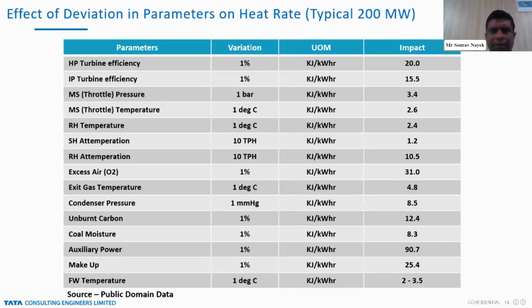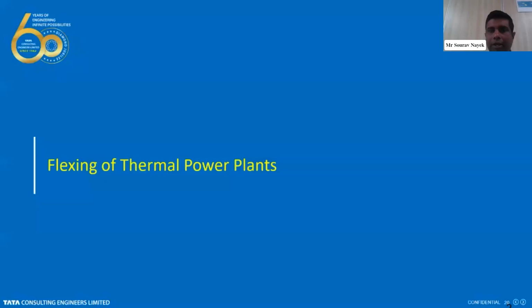We have captured the different parameters and how they impact the heat rate, like the turbine, condenser, and different boiler parameters. For 1% deterioration in turbine efficiency, it impacts almost 15 to 20 kilojoule per kilowatt hour. Similarly, excess air has a large impact, 31 kilojoule per kilowatt hour. Superheater and reheater attemperation, as already discussed, also has an impact on the heat rate. The other boiler parameters, unburnt carbon, moisture in the coal, and excess flue gas temperature increase, all impact the heat rate. There is another significant contribution from the condenser back pressure, which impacts the plant heat rate a lot, and then auxiliary power and makeup water, for which we have talked earlier about the reasons and the corrective actions for heat rate improvement.